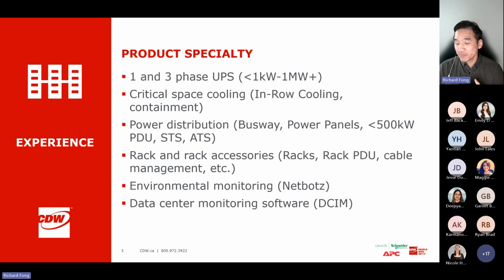It may sound simple enough, but with different voltage standards, current standards, and even connector standards out there, there are different ways to power your IT devices. IT devices nowadays usually have a power supply on the back, usually two. Most customers have two for redundancy, but those power supplies range from 100 to 240 volts - most customers don't even know that.